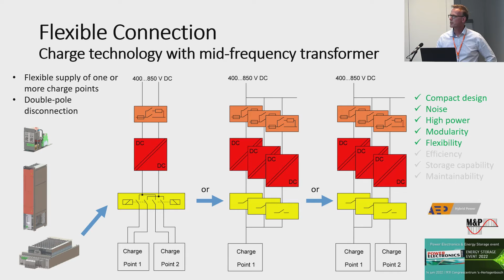If you look at the efficiency of such a converter with mid-frequency transformer and silicon carbide semiconductors, we can reach an efficiency of more than... isn't that good? You see the orange band around the curve - this is the tolerance, it's really hard to measure in this case. You have to have precise measurements to see what the real efficiency is. In our case, we wanted to reach more than 97%, and from the point of 30% of the power, the lower part, we already achieved that with this type of topology.